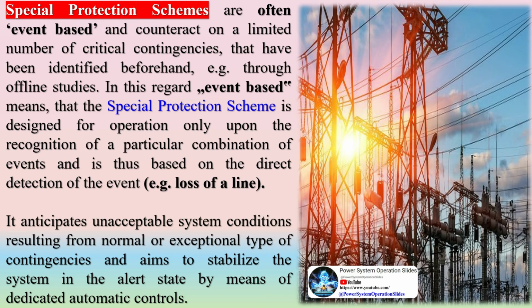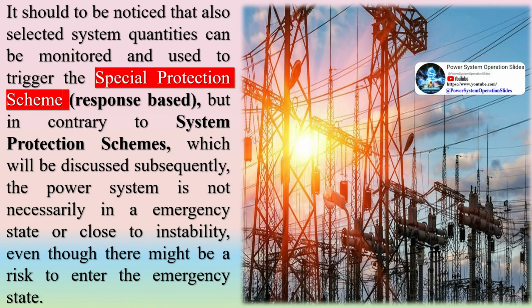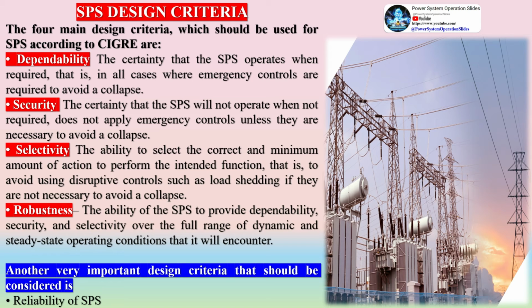In some power systems, an overlay structure, e.g. strong HVDC links, are in operation or planned. Due to economic reasons, these strong links might not be inherently redundant. If there is a lack of redundancy, other measures are necessary to contain normal and exceptional type contingencies and to provide acceptable system performance. The entity of these measures can be pooled under the name Special Protection Schemes. Special protection schemes are often event-based and counteract on a limited number of critical contingencies that have been identified beforehand, e.g. through offline studies. In this regard, event-based means that the special protection scheme is designed for operation only upon the recognition of a particular combination of events and is thus based on the direct detection of the event, e.g. loss of a line. It anticipates unacceptable system conditions resulting from normal or exceptional type of contingencies and aims to stabilize the system in the alert state by means of dedicated automatic controls.